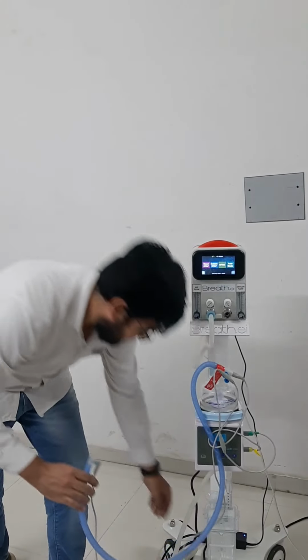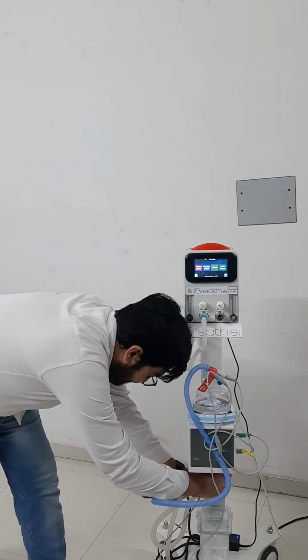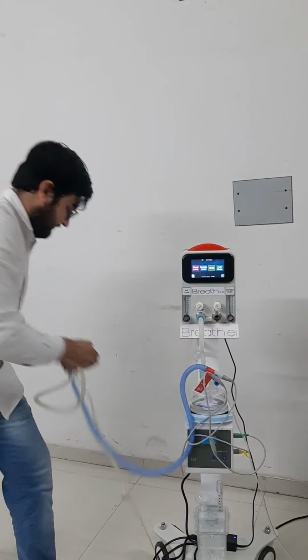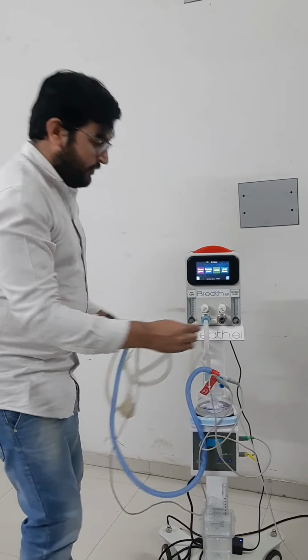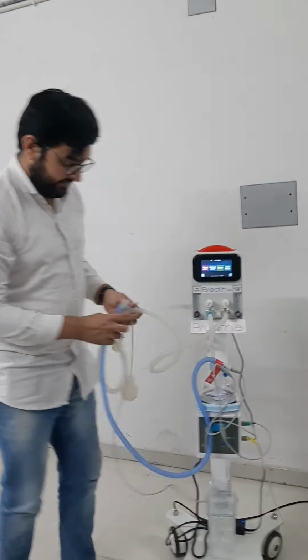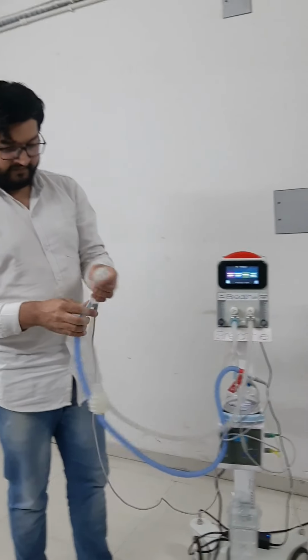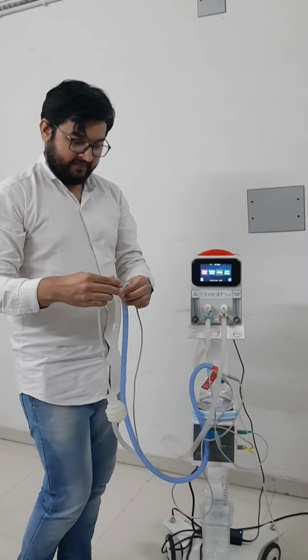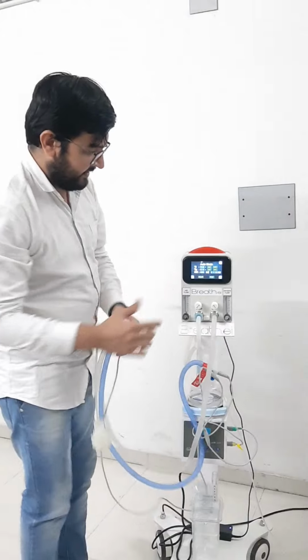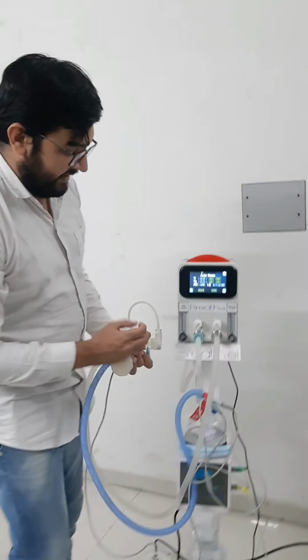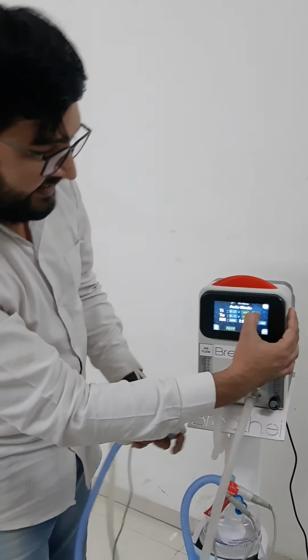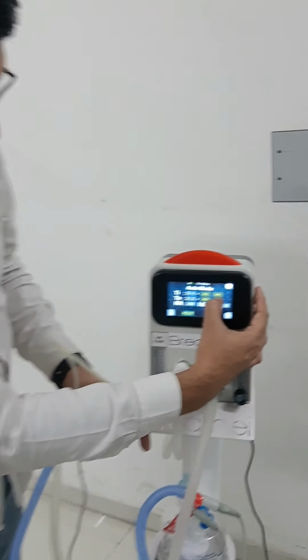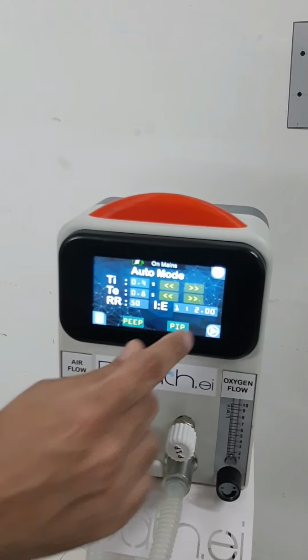And the last and fourth mode is the auto resuscitation mode. For auto mode, you have to connect the expiratory limb to the machine and click on the auto mode. Now you have to set 2 parameters mainly. One is TI and TE. From TI and TE, the RR and I:E ratio will be calculated.